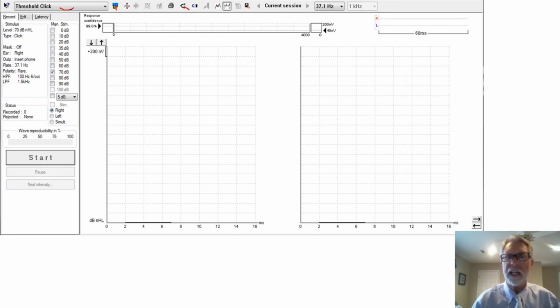If you want to see the contralateral response, it's an icon right there. And of course, this is your selection for a split screen. This is the icon for saving the test and moving on. If you had a previous session on that same patient, you can immediately view it by just clicking right there. Even if there were several sessions, you can bring them right onto the acquisition screen just to observe them so you'd be able to use them to make decisions.